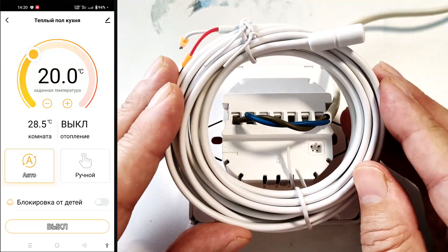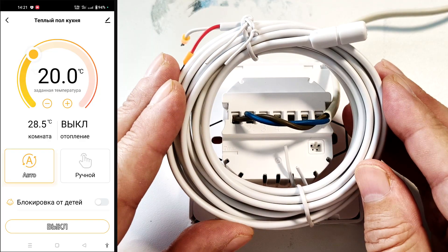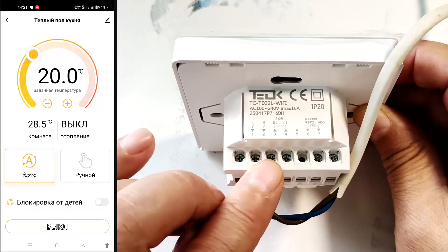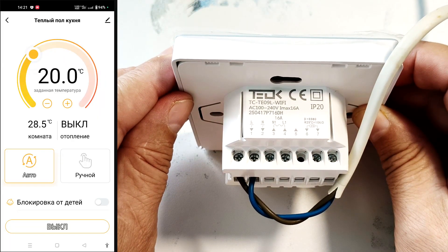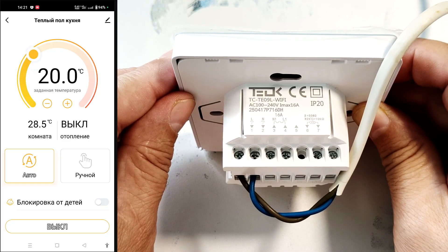The external temperature sensor is connected to the sixth and seventh terminals. A sensor with a 3-meter cord is included in the kit, but another 10-kilohm sensor will also work if connected at the installation location. Before starting, carefully check the correct wiring connections and the tightness of all connections — incorrect connections can cause the thermostat to fail.